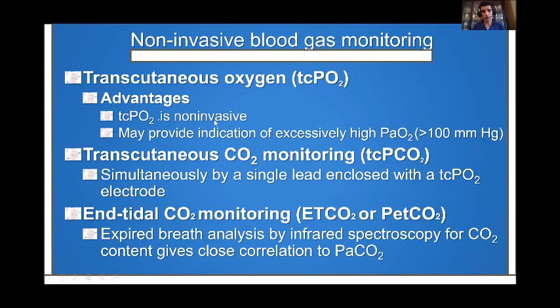The advantage of transcutaneous oxygen monitoring is that it is non-invasive and, unlike pulse oximetry, it is a good way of measuring high values of partial pressure of oxygen. The other type of non-invasive blood gas monitoring is transcutaneous CO2 monitoring, which uses exactly the same principle as transcutaneous oxygen monitoring — with the same advantages and disadvantages.